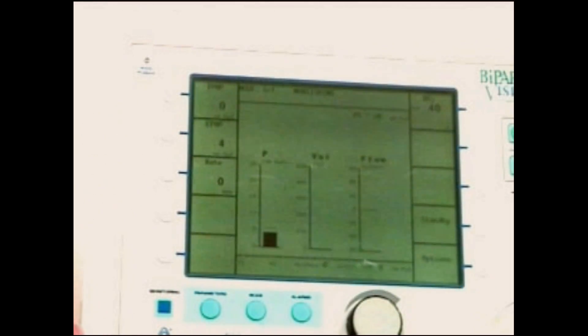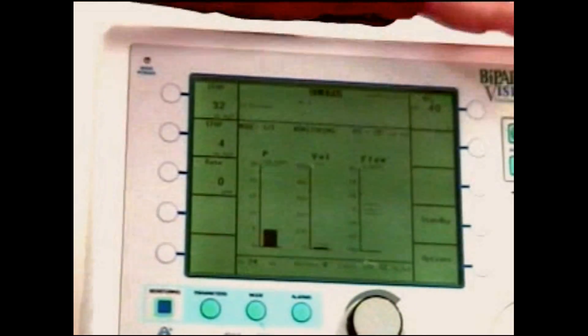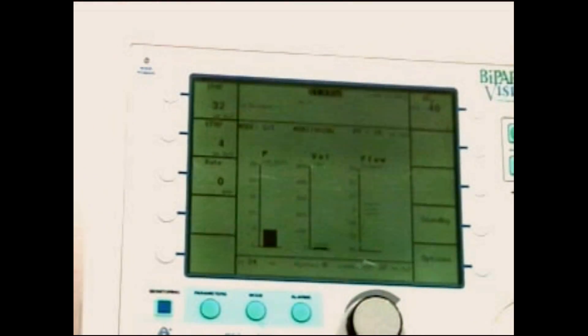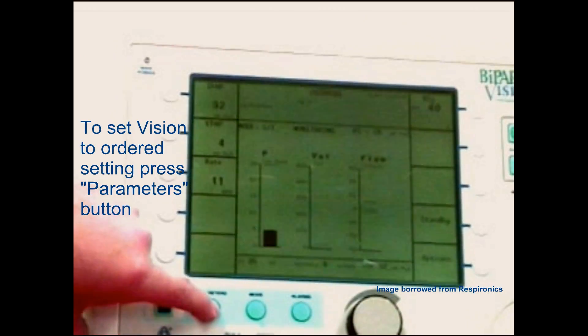Monitoring takes you into the functions of the machine. With this, first before you set it up on the patient, you will need to press parameters.